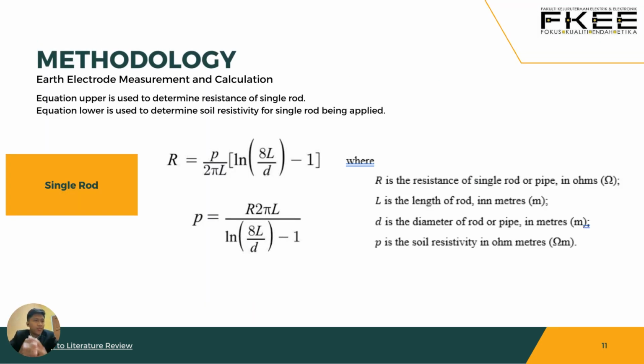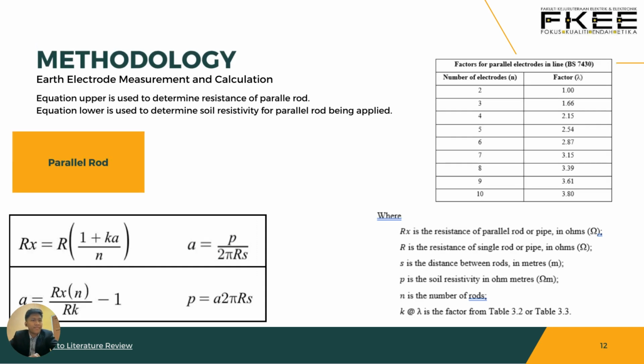This is the formula for a single rod: the upper formula determines the resistance of the single rod, and the lower determines the soil resistivity for the single rod. For parallel rods, the upper formula determines the resistance, and the lower formula determines the resistivity for parallel rods applied to that type of soil. I have provided a table for the constants, which we can refer to.